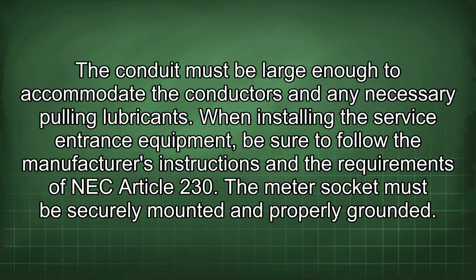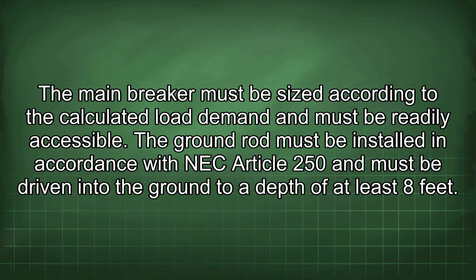When installing the service entrance equipment, be sure to follow the manufacturer's instructions and the requirements of NEC Article 230. The meter socket must be securely mounted and properly grounded. The main breaker must be sized according to the calculated load demand and must be readily accessible. The ground rod must be installed in accordance with NEC Article 250 and must be driven into the ground to a depth of at least 8 feet.